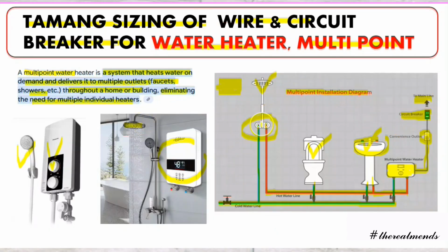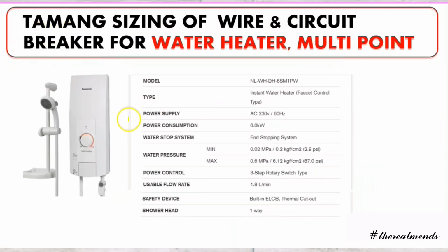To start with the computations, we have the specifications of our multi-point water heater. It is an instant water heater. The power supply is 230 volts, single phase, at 60 hertz. The power consumption is 6 kilowatts. So this water heater consumes a lot of power. And then there is a water stop system, and so on. For our safety device, a built-in earth leakage circuit breaker, thermal cutout, known as ELCB. Those are the common specifications of a multi-point water heater. There are other ratings, like 4.5 kilowatts, 6 kilowatts, but for this we use the maximum, 6 kilowatts. It is commonly used.